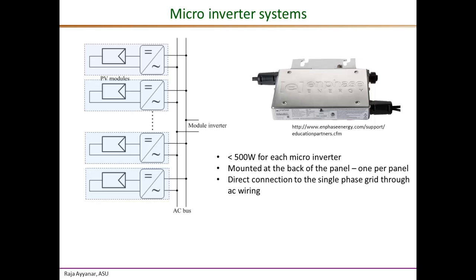The concept of the microinverter has been gaining a lot of traction recently. The concept is to have one inverter per PV module, mounted right at the back of the module itself, and in some cases integrated into the module during its design — sometimes called an AC PV module. Since they are attached to the module, the rating corresponds to that of the module, typically in the 250 to 300 watt range. A key advantage is that only AC wiring is needed, connected in a daisy-chain fashion to the AC grid, eliminating DC wiring and DC circuit breakers.